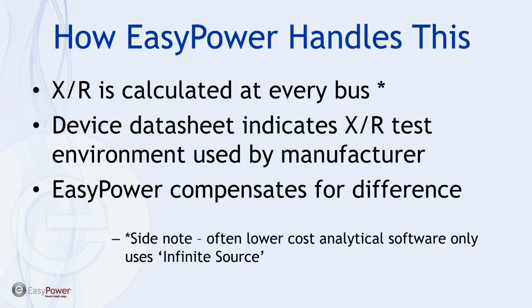So when we get into the software itself, EasyPower actually calculates the X over R at every bus. And once we have identified the protective device that's being utilized on that particular bus, then the data sheet information from the manufacturer is used as the reference point, and we compensate for the difference in what's being measured versus how the device is being applied in the system. The analysis is being applied in our one-line diagram.